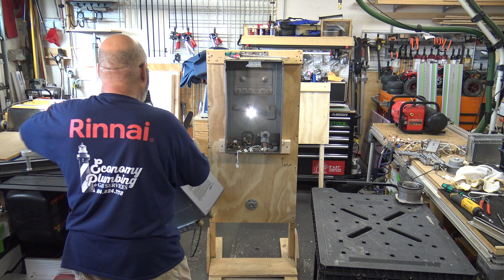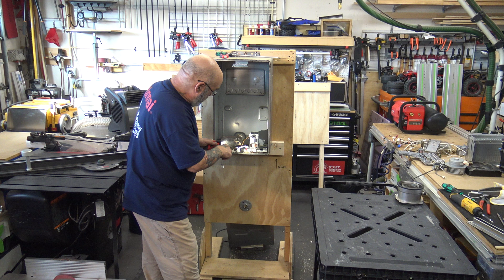All right, so now what do we need to do? I would hit this with a vacuum, and I would pull out this O-ring and put the new O-ring in. I would take my Dremel and clean in here real good, because you got to get the new heat exchanger and the new O-ring in there. So clean in there real good.